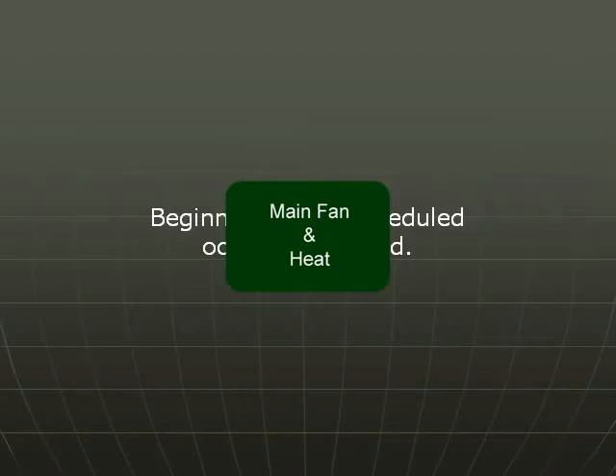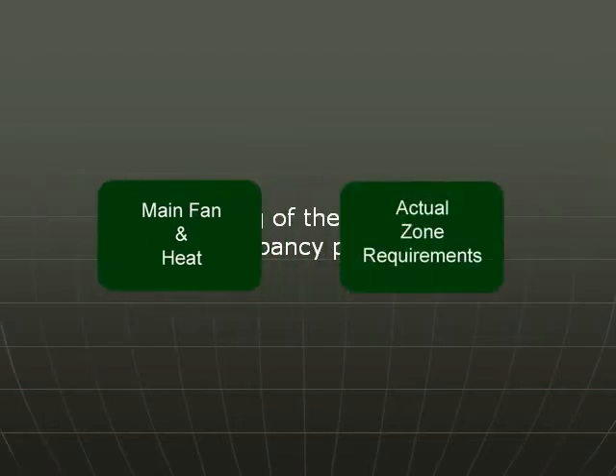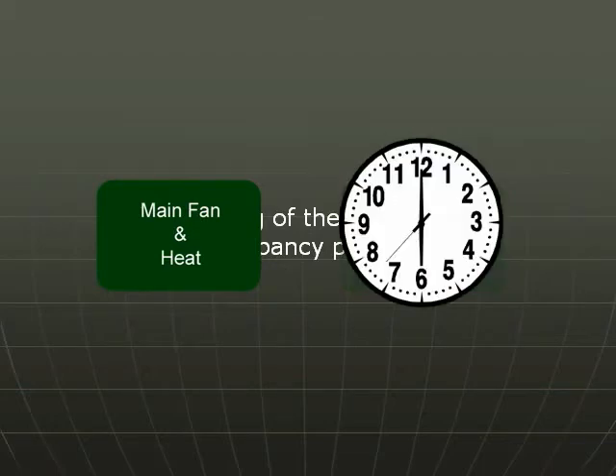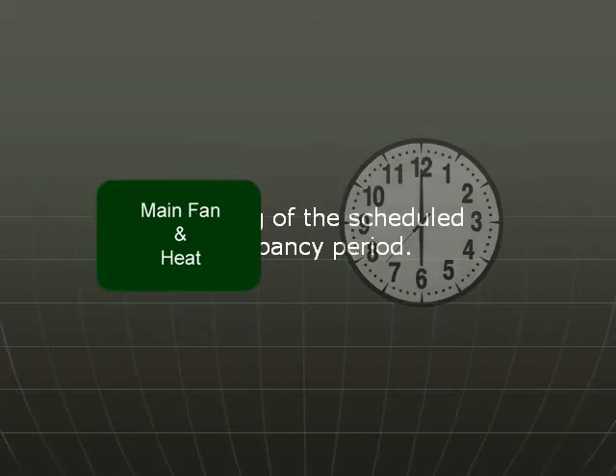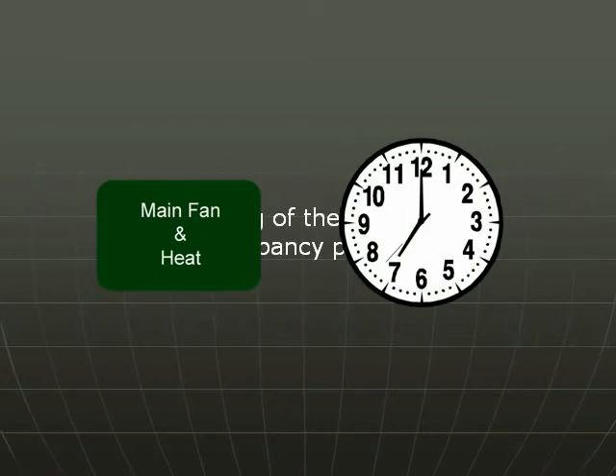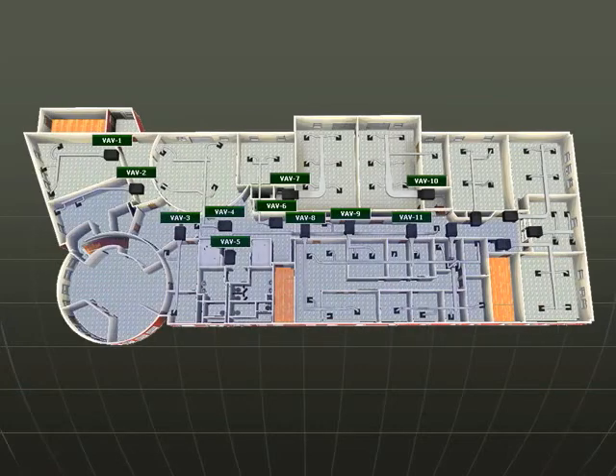The main fan system and heating system is started based on actual heating requirements from any of the zones requiring heat. Example: normally the fans in the heating system are scheduled to start at 6 a.m. Now they can start later and at reduced capacity to meet the actual heat load requirements.